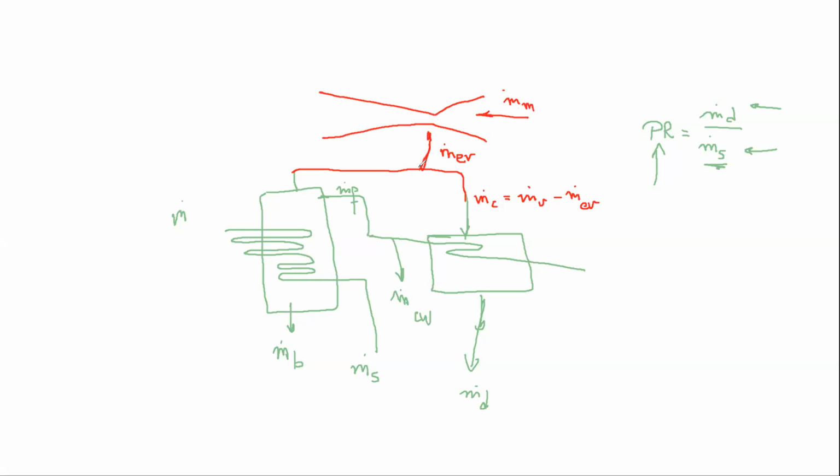And this vacuum is what's responsible for extracting that m dot entrained vapor here. It is going to mix with the motive steam and it will go through the diffuser part, and the diffuser part is where the velocity decreases and the pressure increases. So we call this a thermovapor compressor. And this quantity is going to be the quantity that will enter here. So m dot motive plus m dot entrained vapor.